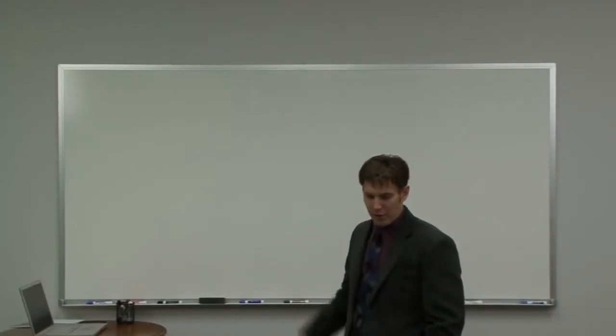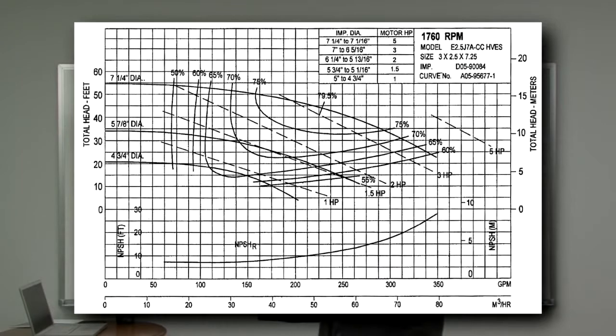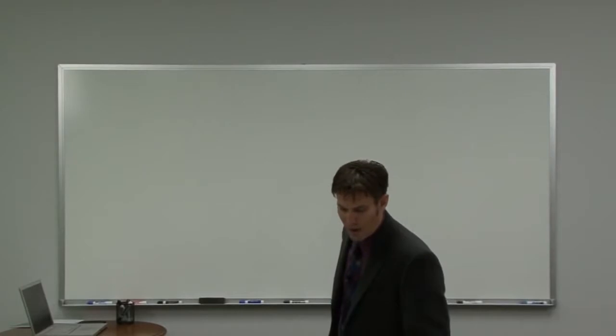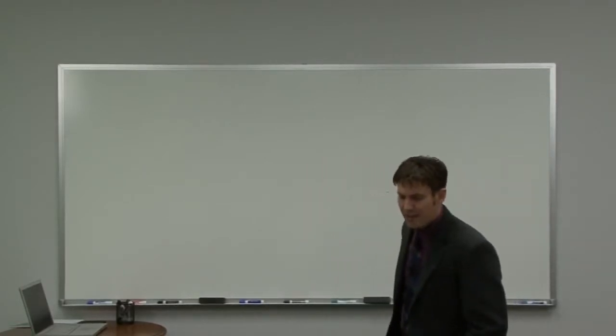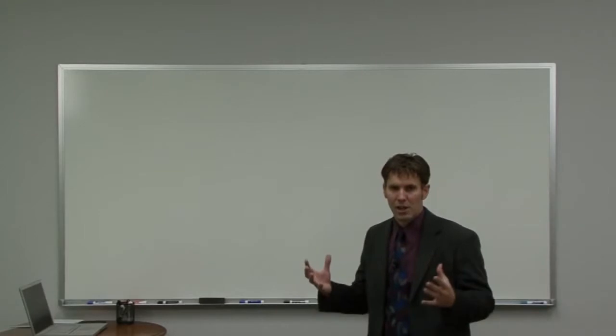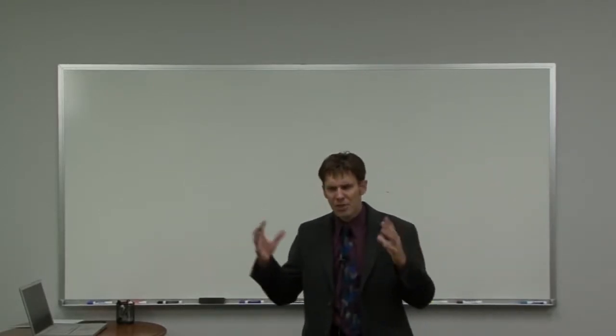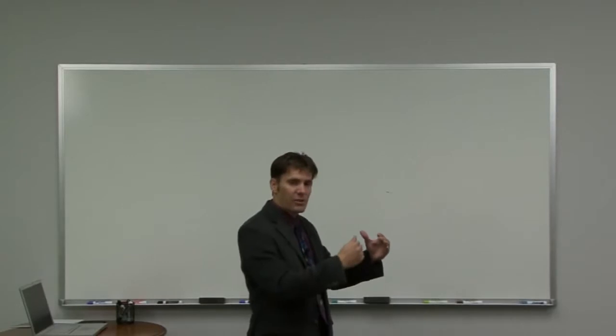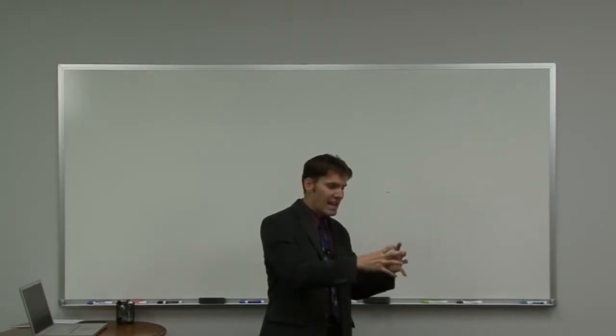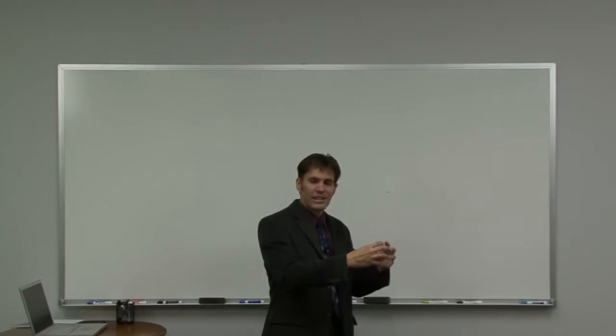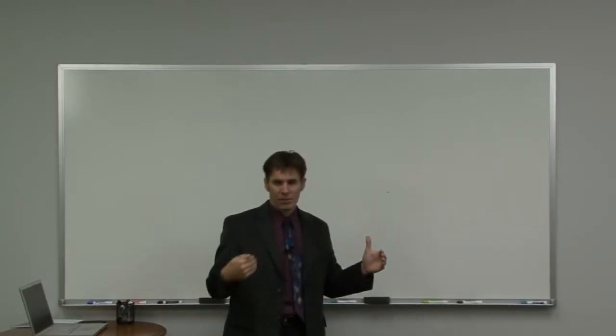Let's put up an actual pump curve from Patterson pumps that we can look at and analyze and understand everything that they're displaying on the pump curve. This is the Patterson pump model E2.5J7A-CC from their HVES series. It's a horizontal end suction closed coupled pump. The CC stands for closed coupled. Now, typically most manufacturers, whether it's closed coupled or flexible coupled, it's typically the same curve. Why? Because they're using an end suction pump. It's using the same volute. It's also using the same impeller. It's just that the drive assembly has changed.